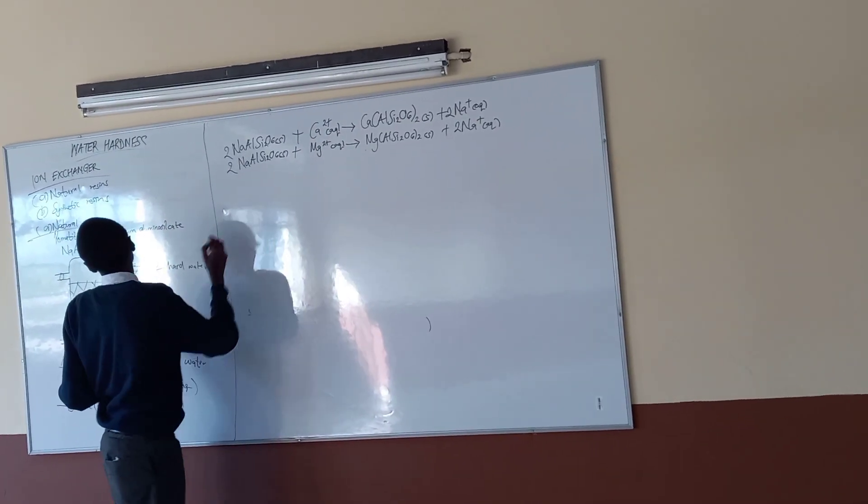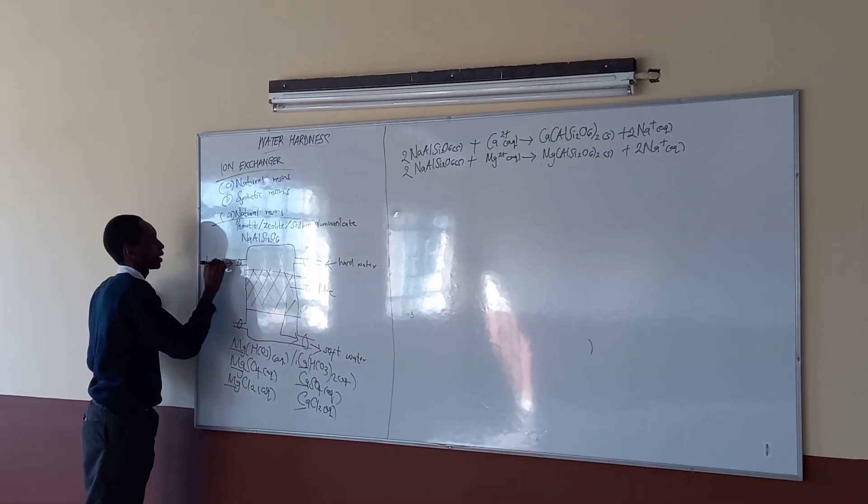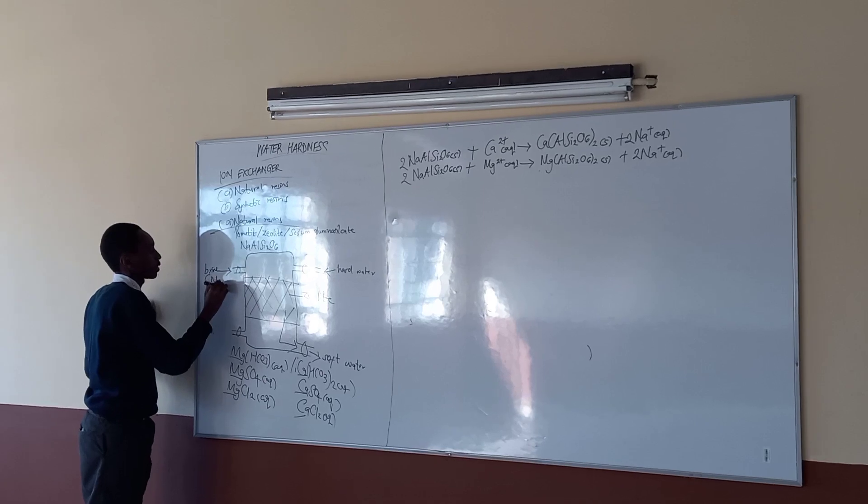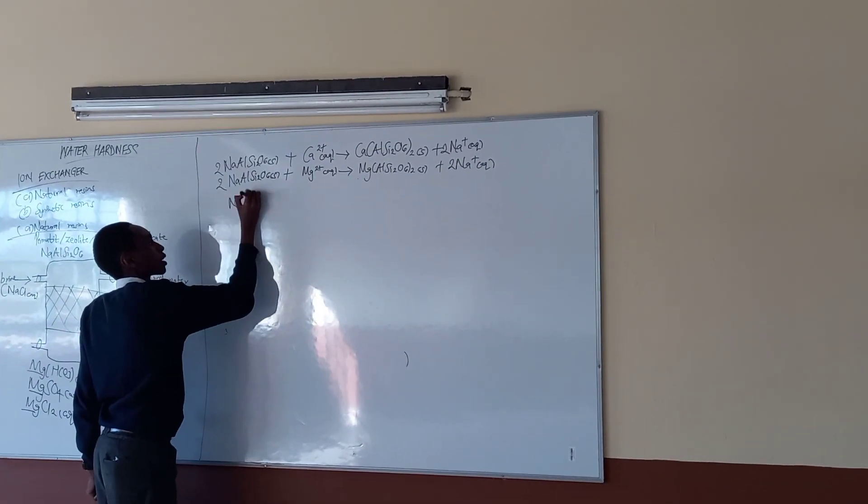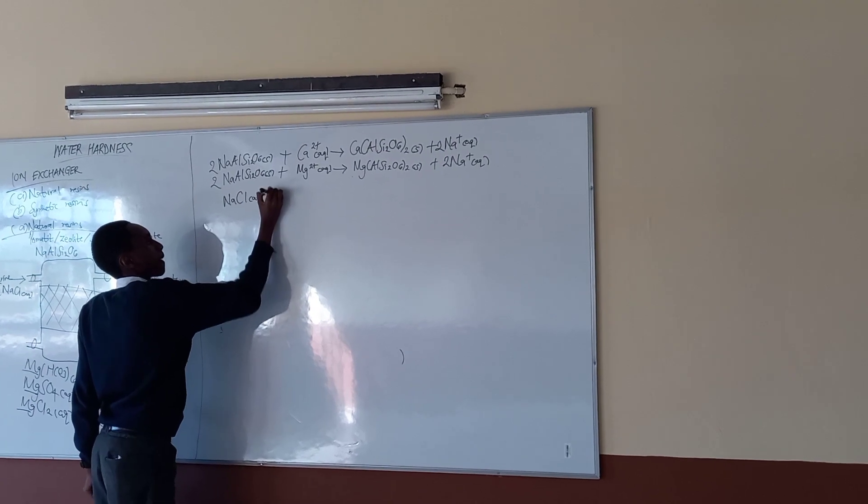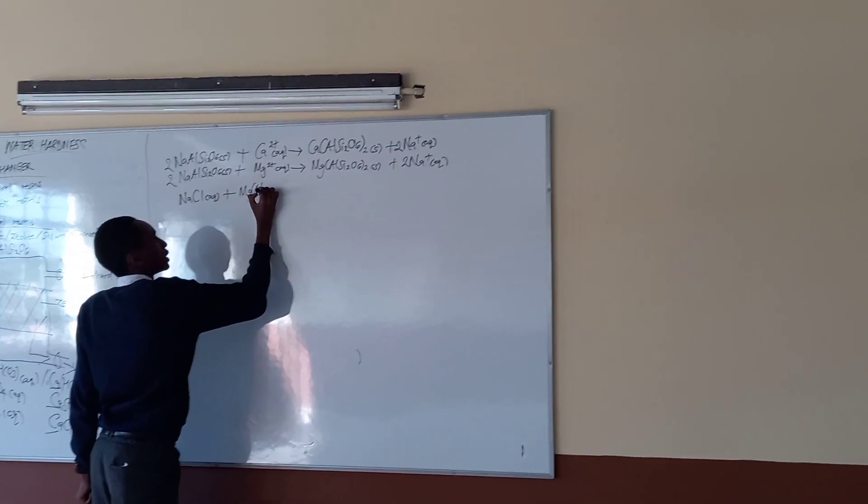So the calcium aluminum silicate or magnesium aluminum silicate is in the tank, and we want to restore the sodium aluminum silicate. So, we will bring in brine through this pipe. Brine is sodium chloride aqueous. Sodium chloride aqueous plus magnesium aluminum silicate solid gives sodium aluminum silicate solid plus magnesium chloride aqueous.